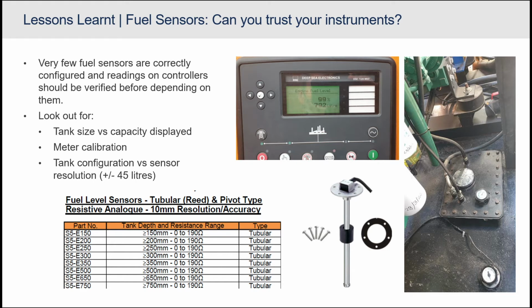What I'm saying is, initially when we get to generators, I haven't experienced one where the fuel sensors, for instance, have been calibrated correctly. So what is the first thing that is normally the problem? So the tank size versus the capacity displayed. Most of these controllers, for instance this DeepSea controller, as far as I know, the default setting is normally 1,000 liters. So as soon as you install it, if you don't set it up and make your own measurements and determine the fuel capacity of your specific tank, then it will probably show you 1,000 liters. And we've seen that a lot.